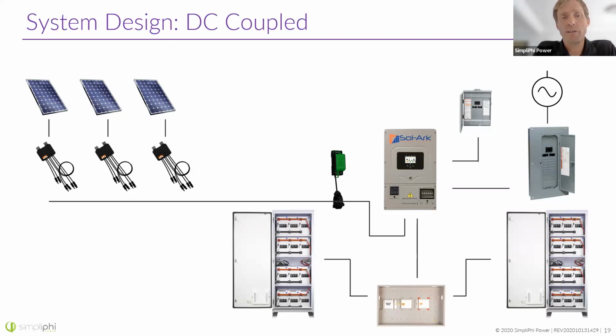Some of these devices will take several panels in, 2 panels, but there are power limitations and current limitations on the rapid shutdown modules. The transmitter that I was mentioning sends a keep alive signal through the PV wires. And so it sends a signal, and as long as the panels are receiving that same signal, those rapid shutdown modules act as closed switches. As soon as that signal disappears, somebody hits the rapid shutdown button, or for any reason that transmitter stops transmitting, those rapid shutdown modules open circuit and the panels stop producing power.